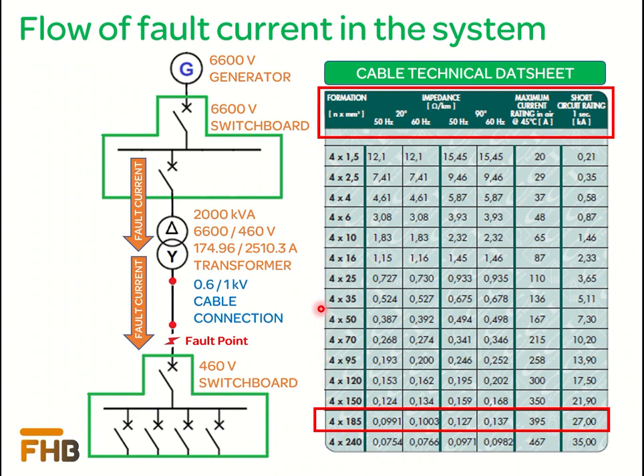To keep the relation with our last video, we are considering the same 2000 kVA transformer with 2510.3 ampere secondary current. For today's calculation we are considering low voltage power cable of 185 mm².